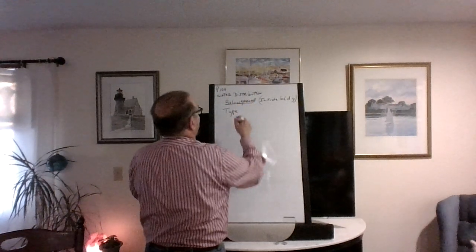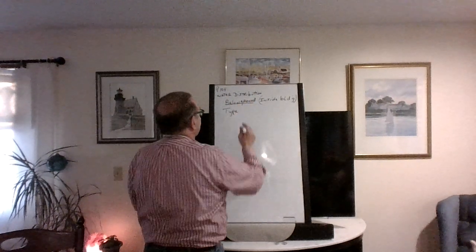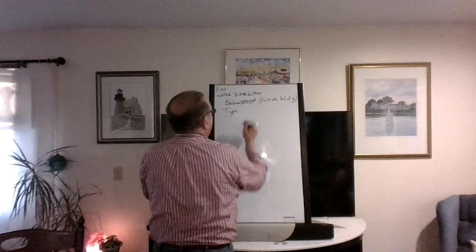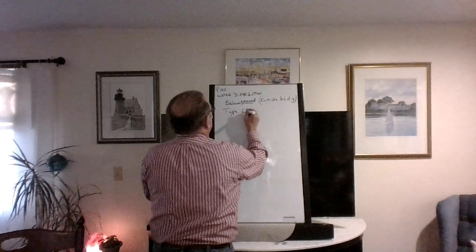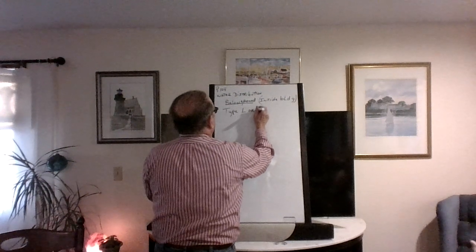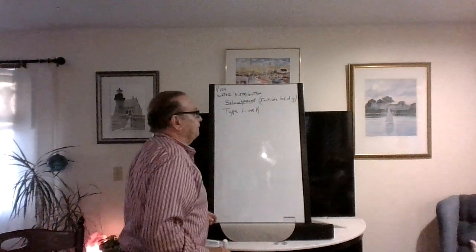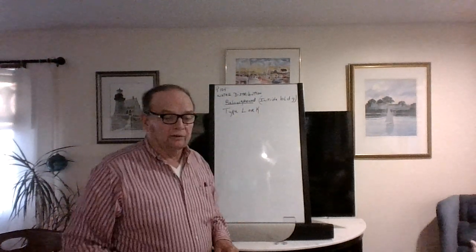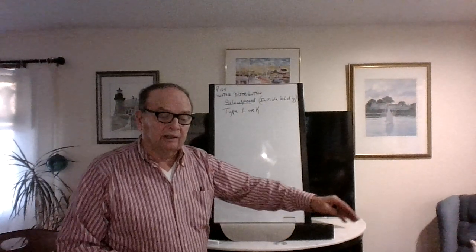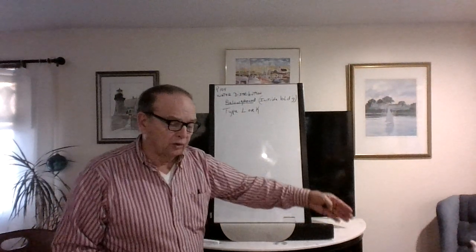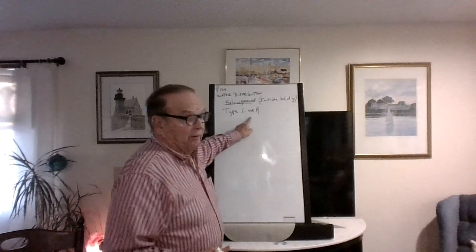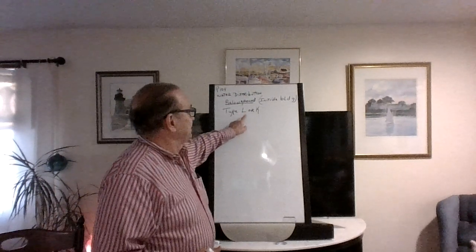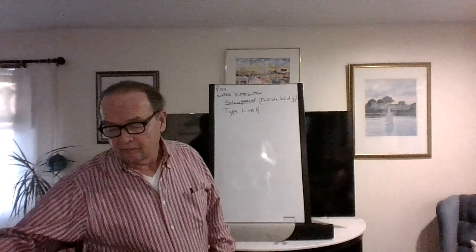But below ground water piping under the floor of the house would be either type L or K. Okay? Both of them are legal inside the house. Now, this is not water service coming in. We've already come into the house. In other words, we're past the meter. We're in the house. All right. You have to go back under the floor. All right. So this would be L or K is legal.